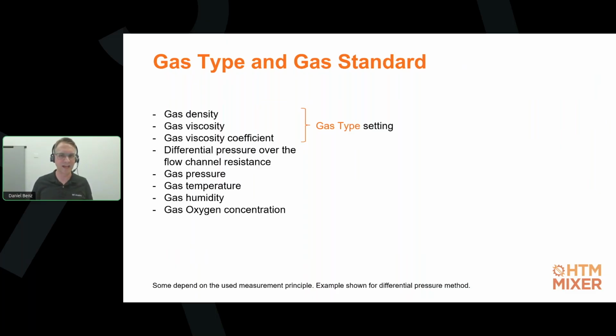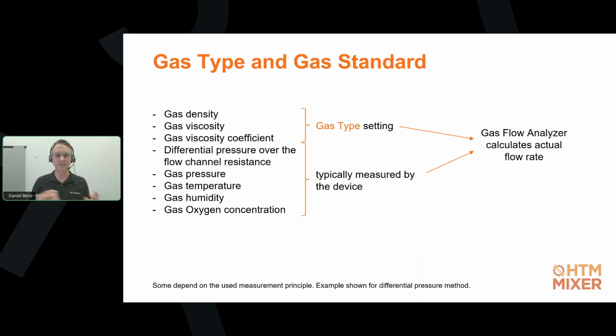You will see that setting on any gas flow analyzer. We need to tell the device if we want to measure flow or volume, for example, of air, oxygen, or a mix of air and oxygen, but we could also say CO2. We need to tell the gas flow analyzer what gas flow we are going to measure. Other parameters, like all the others on the list in this example, are measured by the gas flow analyzer, for example gas temperature, gas pressure, and oxygen concentration. With all these set and measured values, the gas flow analyzer can then calculate the actual flow rate passing through the device. And as we all know, volume is just flow over time, so the same applies for the volume. We consider this process gas flow measurement.